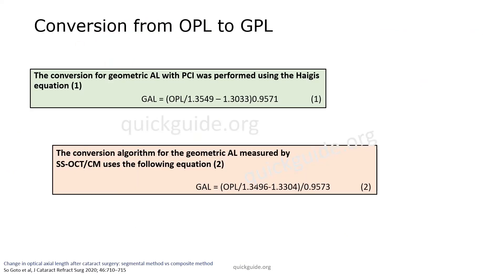These are the two equations used by IOL Master when it was first launched on partial coherence interferometry. The first equation was used by Haigis to convert the OPL into the geometric axial length. The swept-source OCT machine, the IOL Master 700, also has its own algorithm to convert from the OPL to the geometric axial length, given in equation number two.